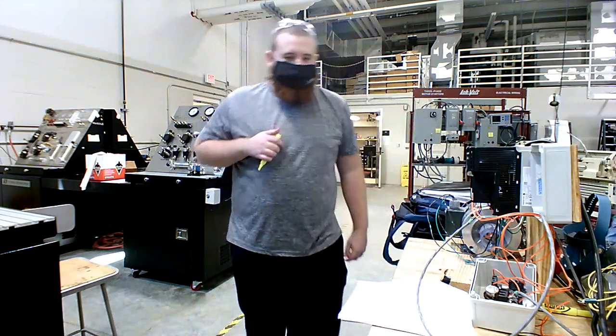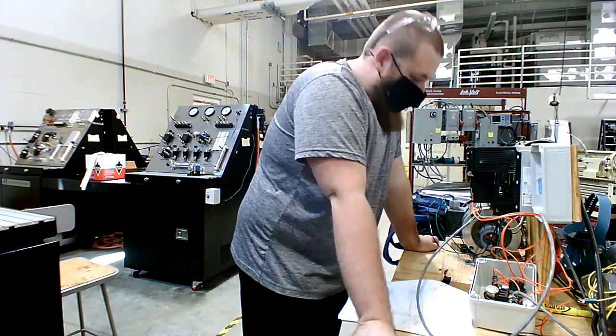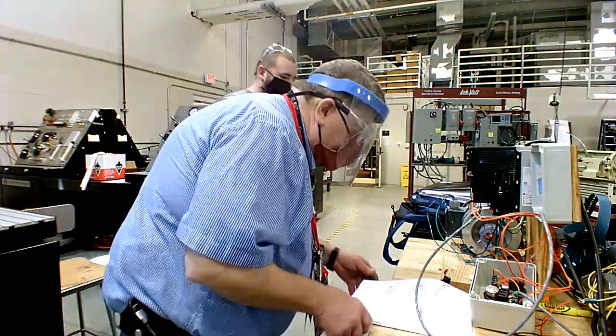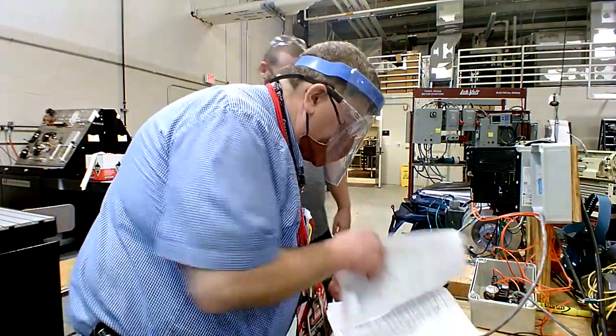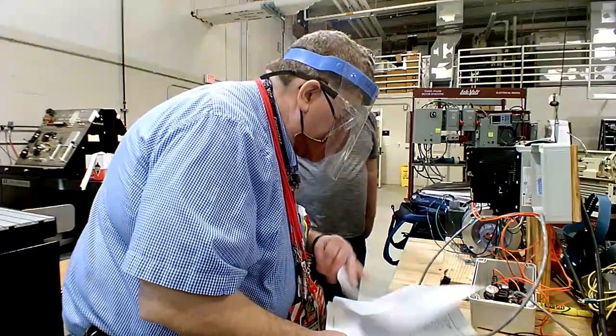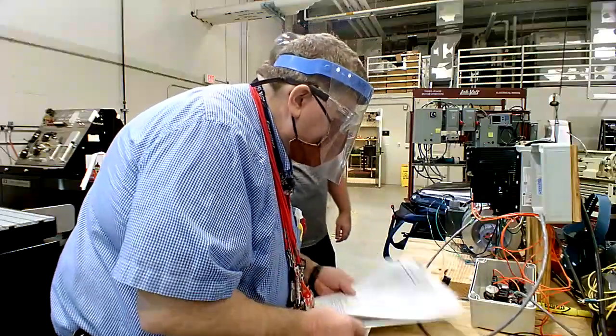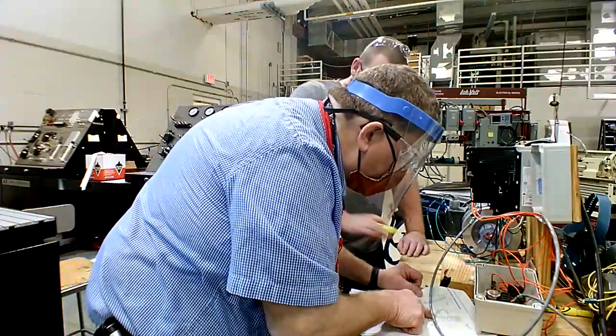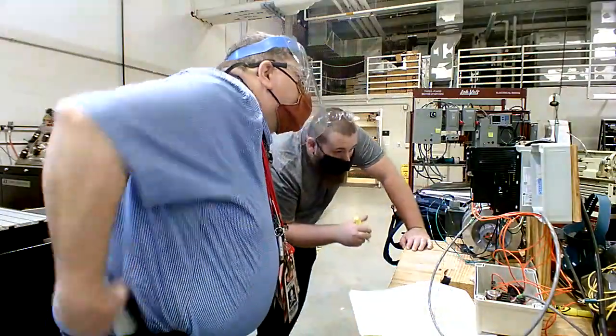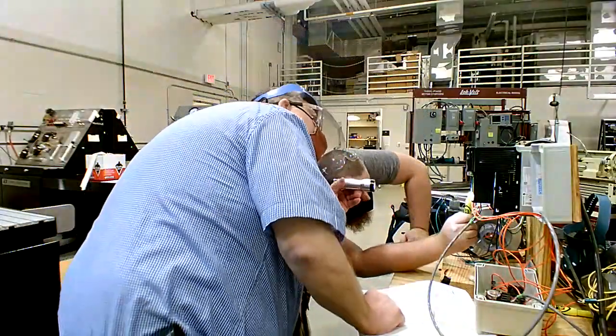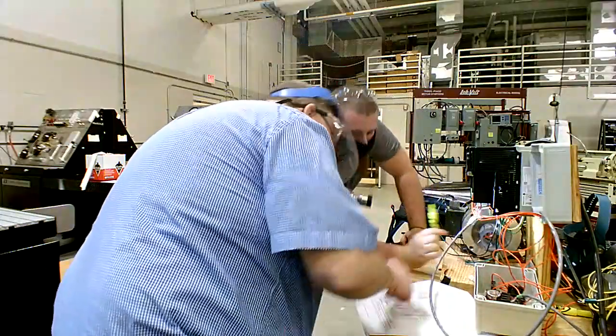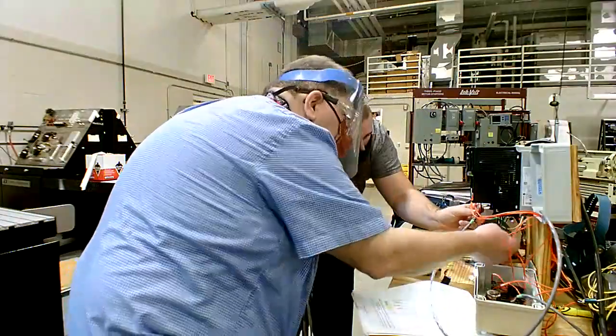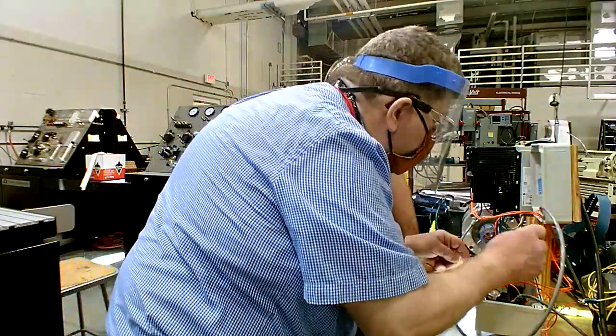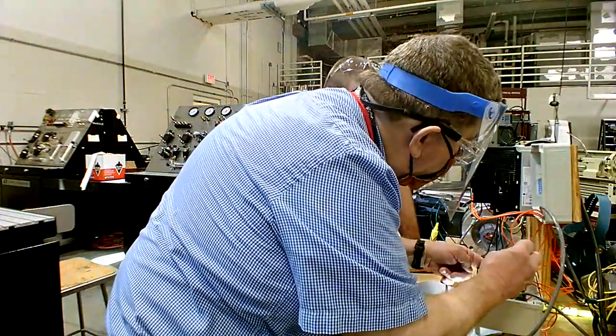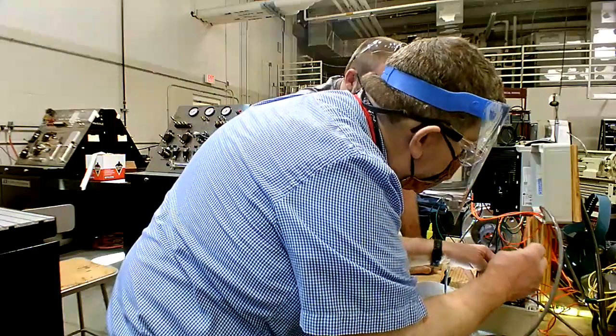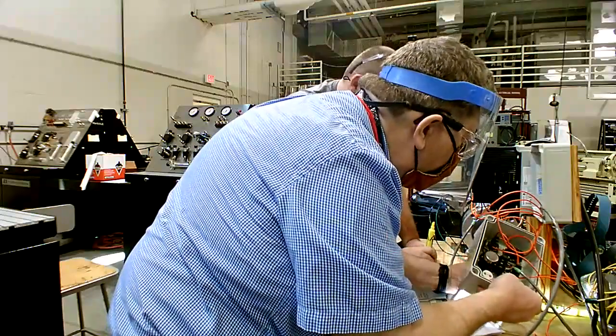So Ben, I've got it written down here to give you 3 bugs on that board. Okay. Now, let's see here. So on this one, your wiring. Circuit 11. 11 will be started on the gray area. Yeah. So 11 will be 24 volts. You took it on. You jumped it around, you sent it to stop, you sent it to start, you also sent it to the forward reverse switch.